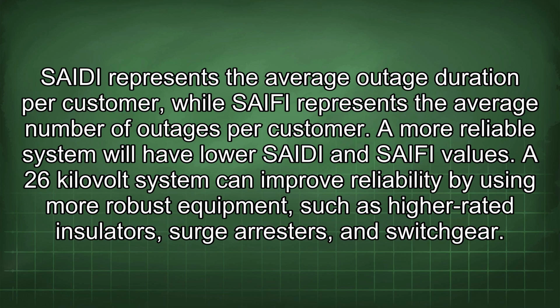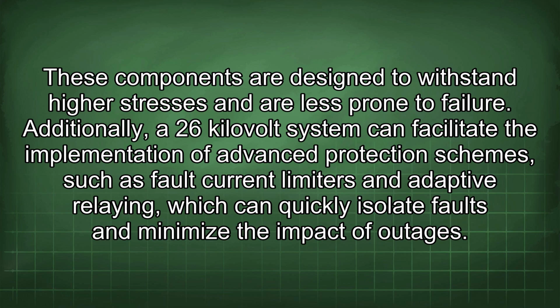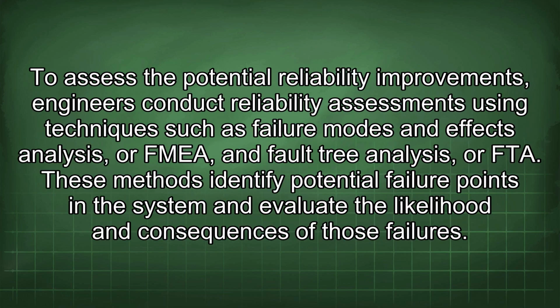A 26 kV system can improve reliability by using more robust equipment, such as higher rated insulators, surge arresters, and switchgear. These components are designed to withstand higher stresses and are less prone to failure. Additionally, a 26 kV system can facilitate the implementation of advanced protection schemes, such as fault current limiters and adaptive relaying, which can quickly isolate faults and minimize the impact of outages. To assess the potential reliability improvements, engineers conduct reliability assessments using techniques such as failure modes and effects analysis, or FMEA, and fault tree analysis, or FTA.